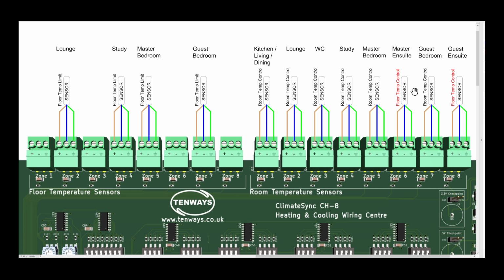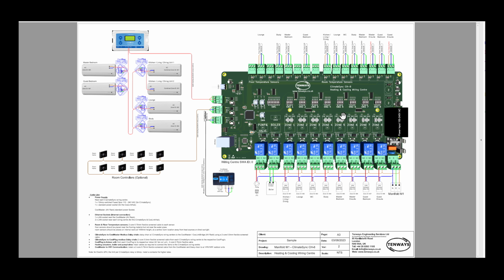The cable to use for that is a screened cable, 0.5 to 0.75 millimeter cable, one of the 2 sizes, and that's a screened cable going to each sensor. So this is the sensors. Now let's have a look at the bottom of the wiring center.